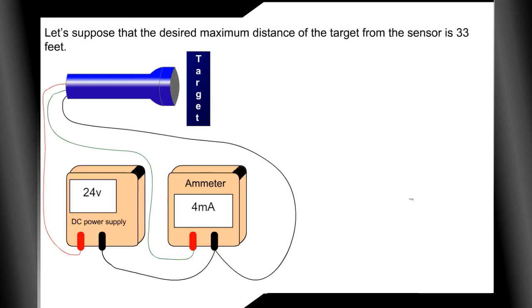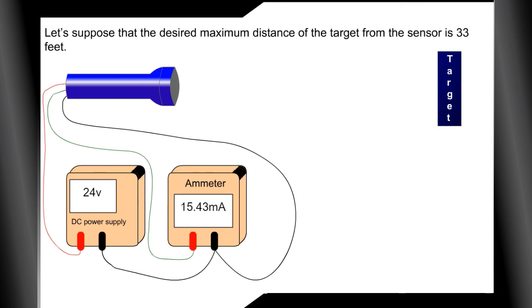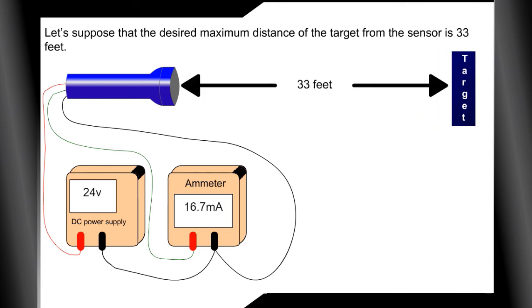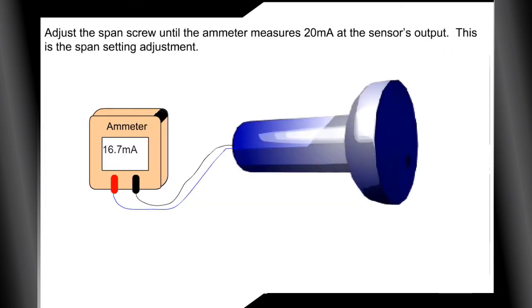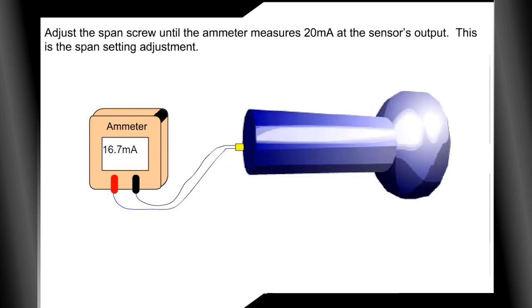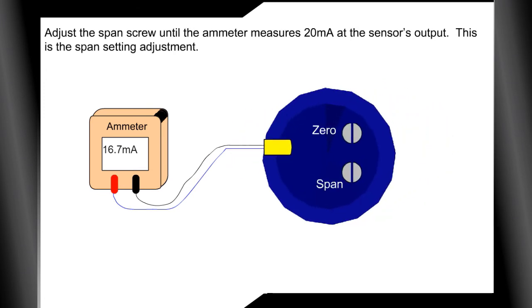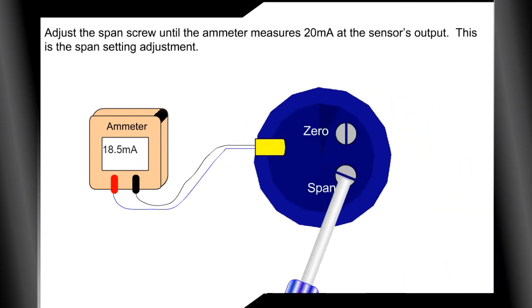Let's suppose that the desired maximum distance of the target from the sensor is 33 feet. Adjust the span screw until the ammeter measures 20 milliamps at the sensor's output. This is the span setting adjustment.